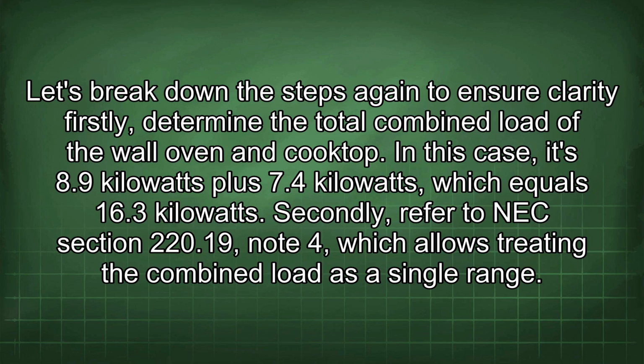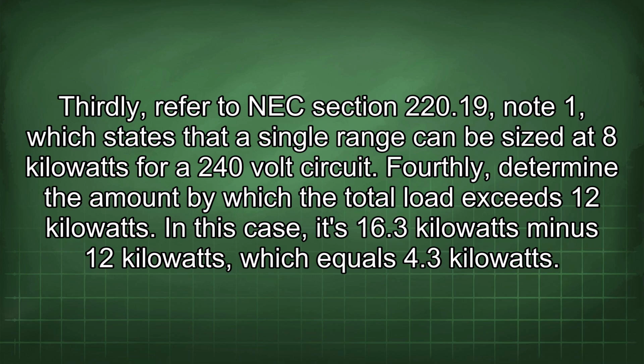Let's break down the steps again to ensure clarity. Firstly, determine the total combined load of the wall oven and cooktop. In this case, it's 8.9 kilowatts plus 7.4 kilowatts, which equals 16.3 kilowatts. Secondly, refer to NEC Section 220.19, Note 4, which allows treating the combined load as a single range. Thirdly, refer to NEC Section 220.19, Note 1, which states that a single range can be sized at 8 kilowatts for a 240-volt circuit. Fourthly, determine the amount by which the total load exceeds 12 kilowatts. In this case, it's 16.3 kilowatts minus 12 kilowatts, which equals 4.3 kilowatts.